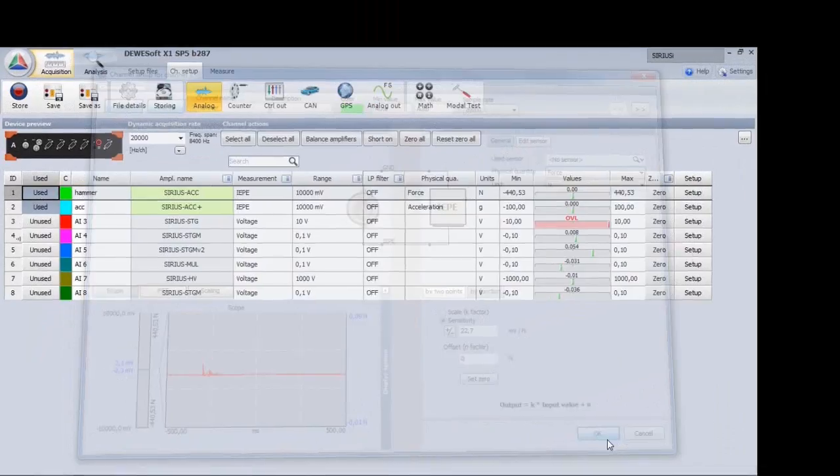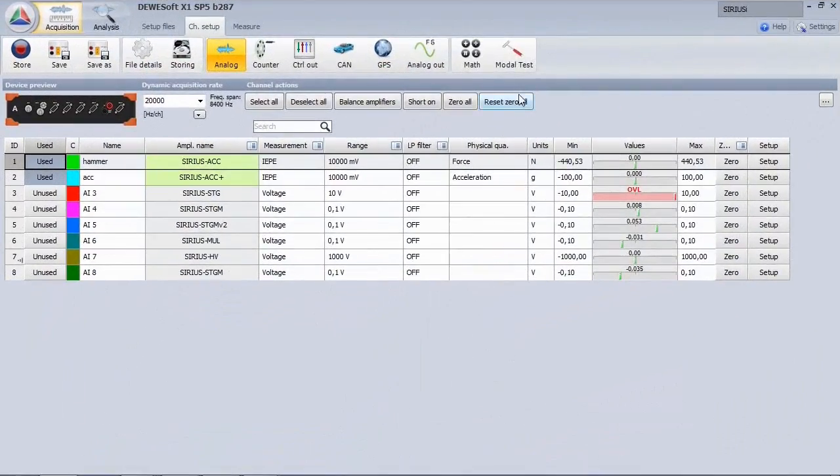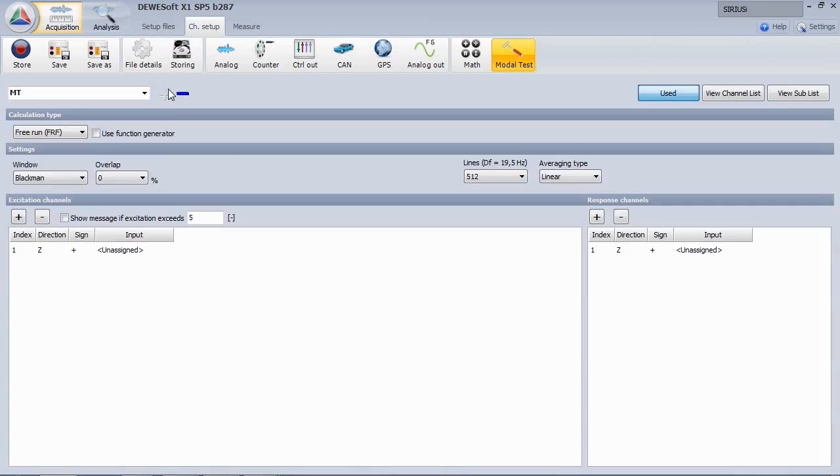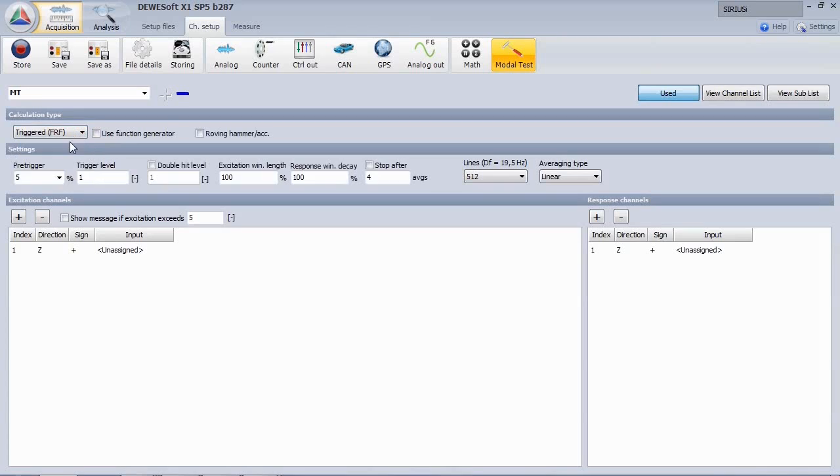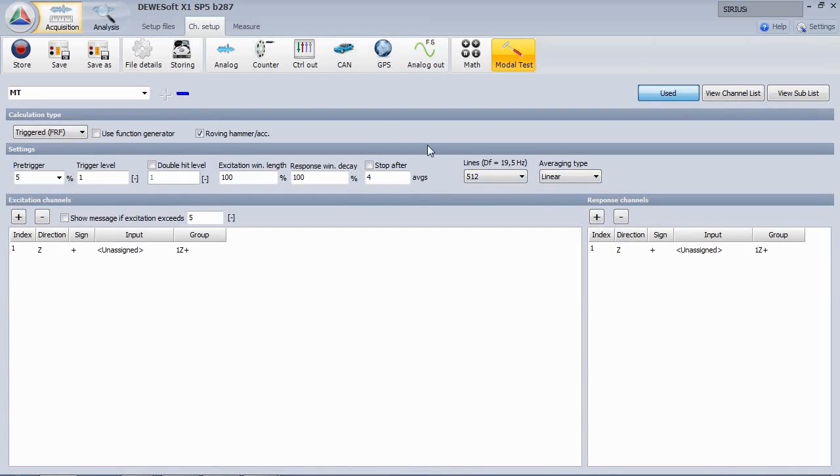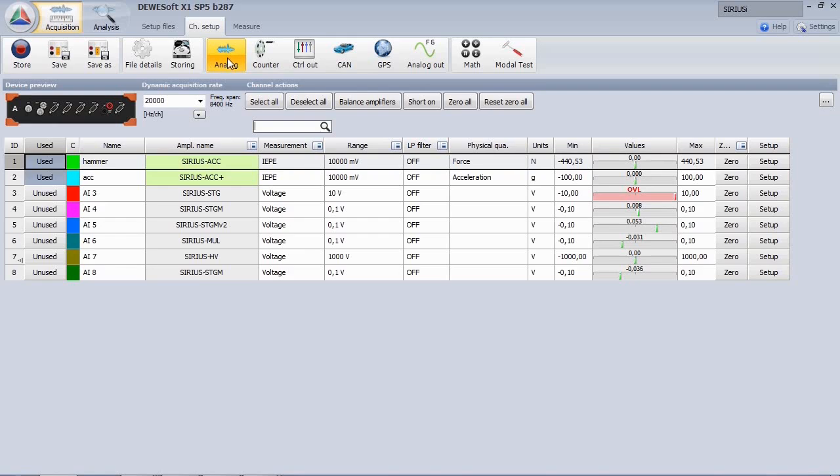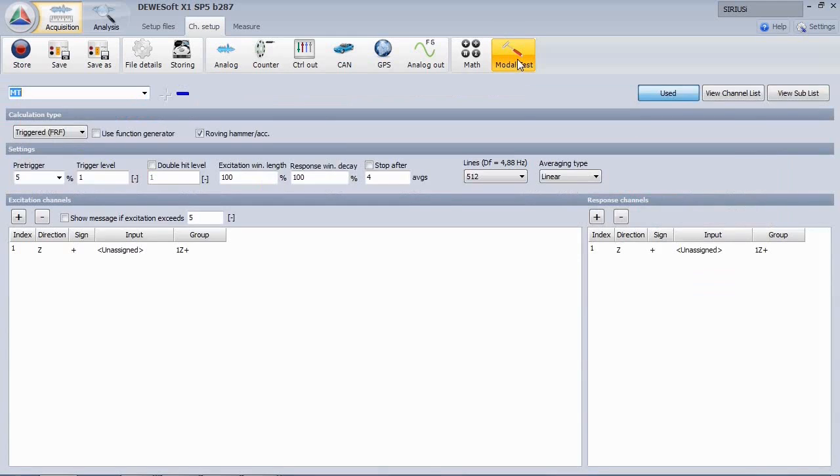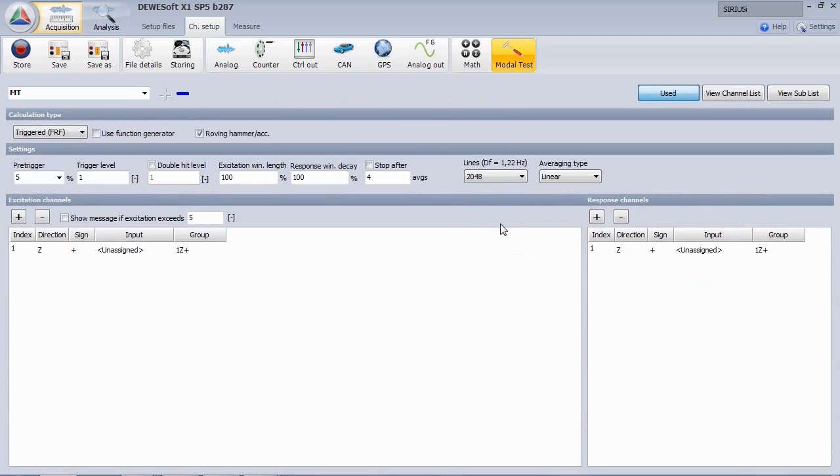Memorize the maximum level we needed for specifying the trigger level. Then add a FRF module, set it to triggered mode with roving hammer. The pre-measurement showed that a trigger level of 1 newton is fine. The FFT resolution is related to the sampling rate. We change it to 5 kHz and 2000 lines, which gives roughly 1 Hz resolution.